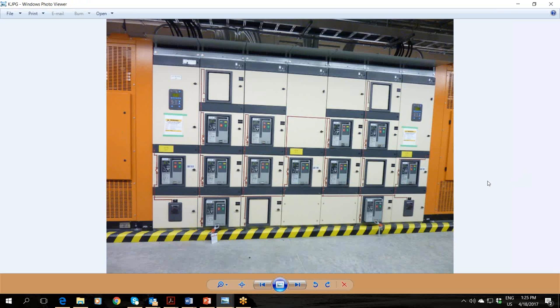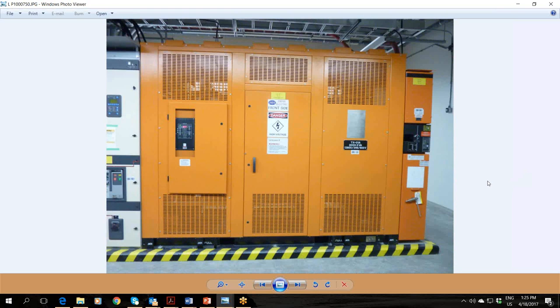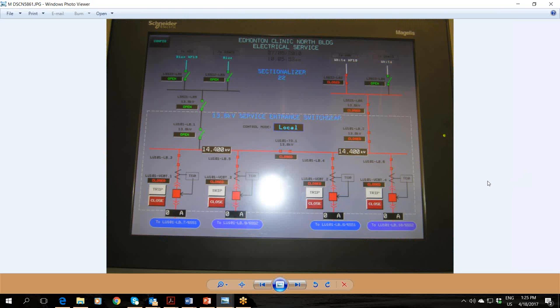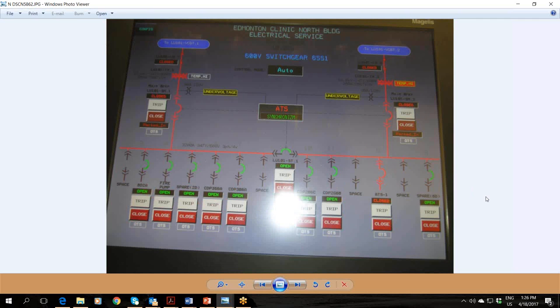In case one side is lost, this main would open, the tie would close, and you have your backup. The other side is again close coupled. This is an example of one of the touch screens that we put in that building specifically. And again, you can operate these medium voltage breakers directly from this touchscreen, just electrically operated through an HMI touchscreen via a PLC control. That control is actually also brought back to our distributed control system.